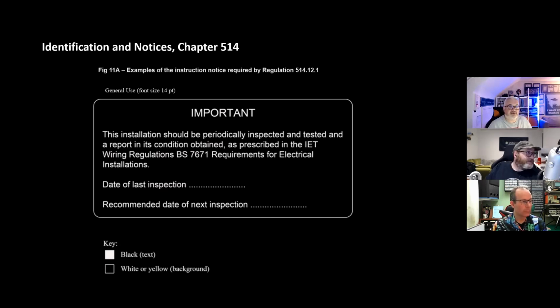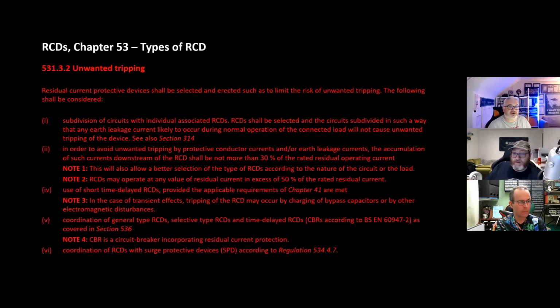There's lots to go through. Just a quick one on this, because I messed this one up yesterday, so I apologize and I hold my hands up. This is the current regulation for unwanted tripping. So this is the split board debate, okay? We know in the last regulations this was introduced: unwanted tripping. Residual current devices shall be selected and erected to limit the risk of unwanted tripping. Following considerations: subdivision of circuits with individual RCDs.